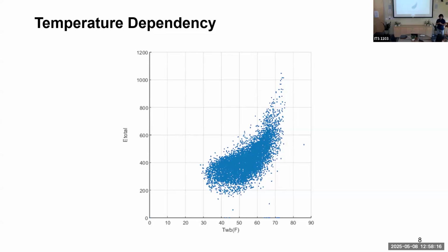And with respect to thermal mass, is it possible to introduce some thermal mass into the building that can be drawn upon very quickly, in a sufficient size to make an impact on these results? Yep. When we were talking to the facility manager earlier, they told us that if the facility was totally empty, with only air inside, then they wouldn't be able to shut it down for 4 hours. Having a lot of product in there that has a higher CP and can sustain its temperature is what allows them to shut down. So increasing that thermal mass does help to drift for longer hours.